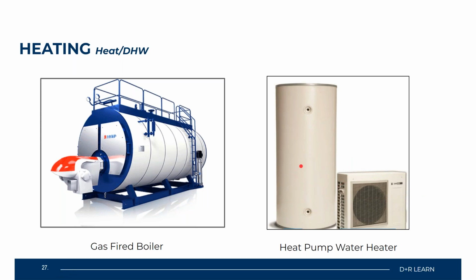Now over to the right, we have our heat pump water heaters, and our heat pump water heaters use electricity to move heat from one place to another rather than generating their own heat like a traditional electric water heater. Now, using these types of systems makes them 2 to 3 times more efficient than your traditional systems. If you understand the refrigeration cycle or the vapor compression cycle, think of a heat pump water heater as a refrigerator working in reverse, or an air conditioning system working in reverse by way of a three-way valve. So for individuals in class today that have HVAC experience, your heat pump water heaters are just air conditioning systems working backwards, if you want to look at it that way.